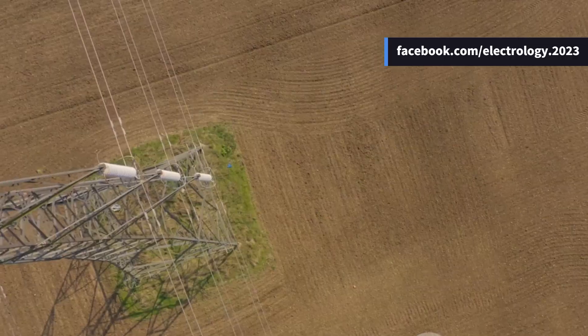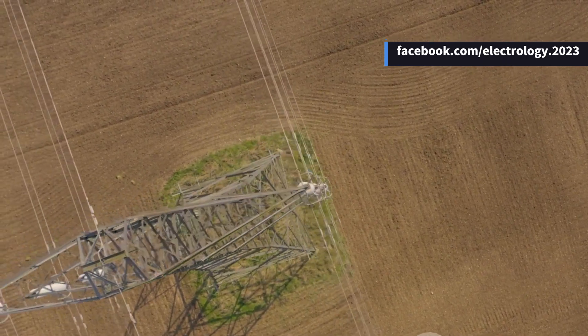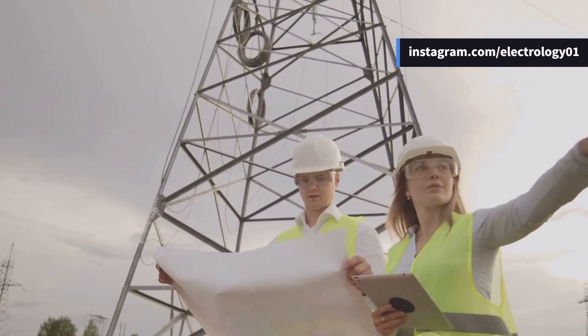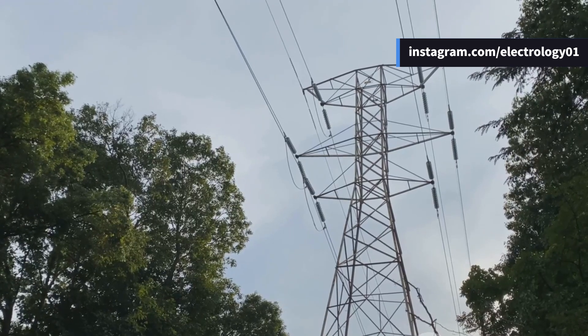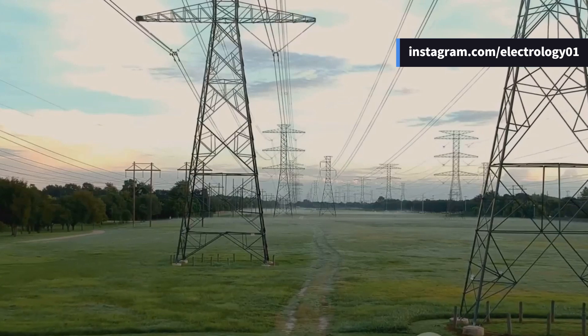But why not use double circuit everywhere? Good question. Double circuit towers cost more, need more land clearance, and are heavier. So they're not the default choice — utilities install them only when demand or reliability justifies it. It's like building a guest room in your house just in case: great, but only if you can afford it.